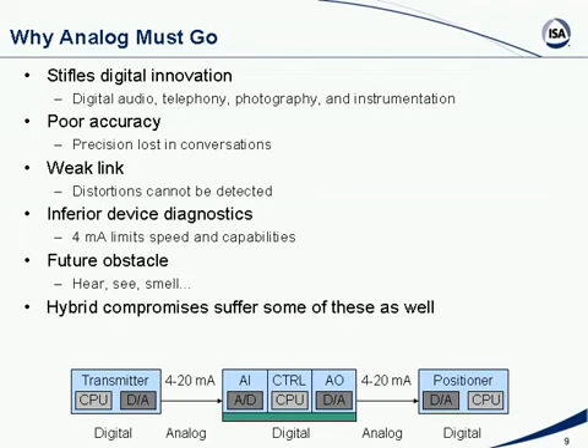And since transmitters are digital, positioners are digital, control systems are digital, it really doesn't make sense to use analog 4 to 20 milliamp anymore. It should be digital all the way. Digital signals, of course, also have higher integrity because any distortion is detected. If you look at an analog signal, if 18 milliamps for some reason becomes 16 milliamps due to high resistance or a ground loop or something, it's very, very hard to detect because it's still a valid signal. But if a digital signal is distorted, it is very easy to detect that through error checking.